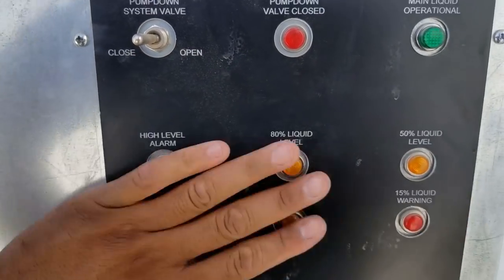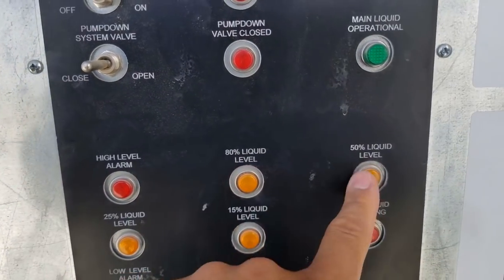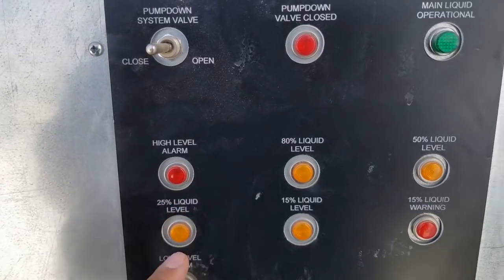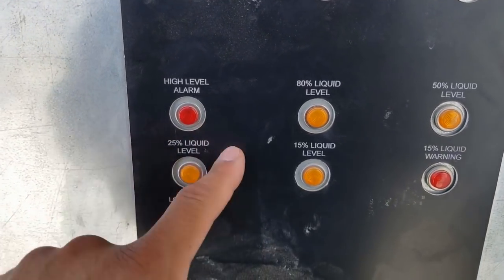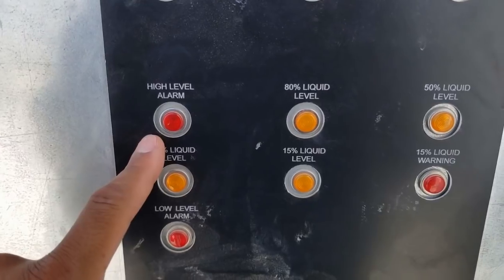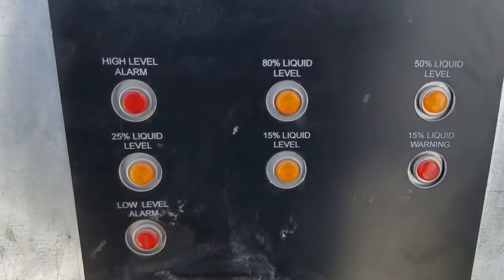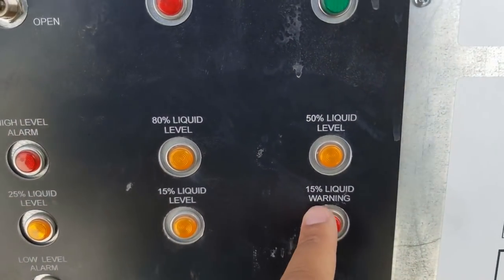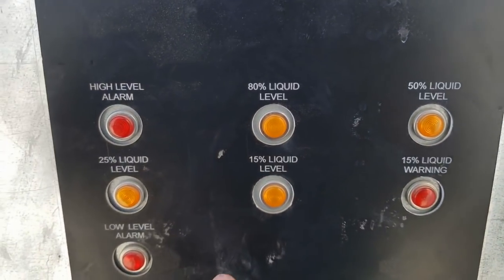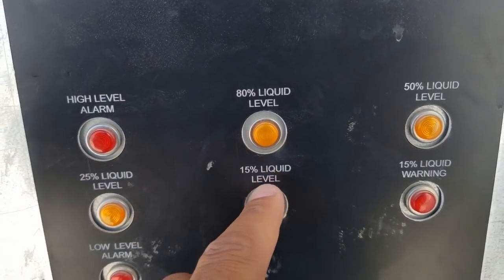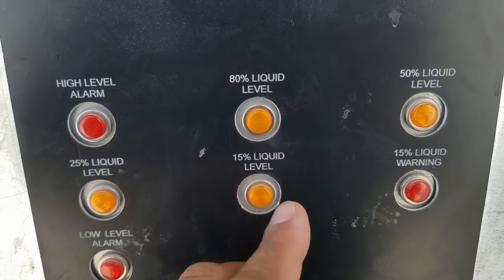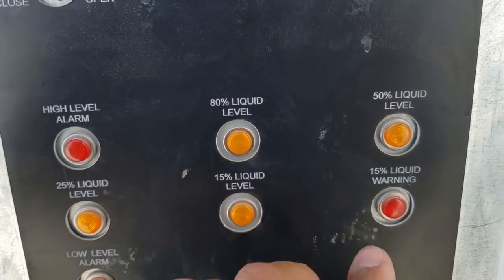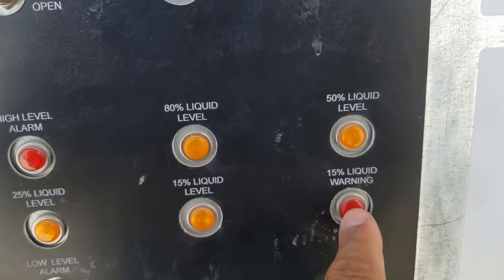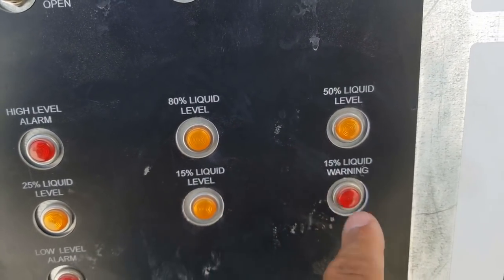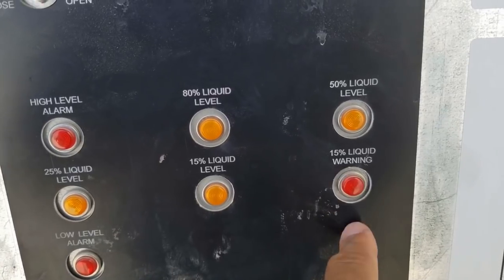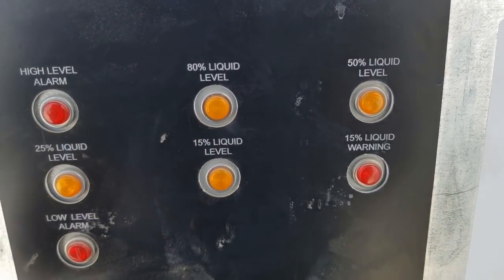Okay, here is the important part. This is your levels. So you want your CO2 level to be around 25. That's your average level that you want. You have a 50% liquid level amber light, which is you're getting low. And then your 15% liquid warning light, which is you're in the red zone. You want to start taking a look at that, adding CO2, try to find where that leak is from.